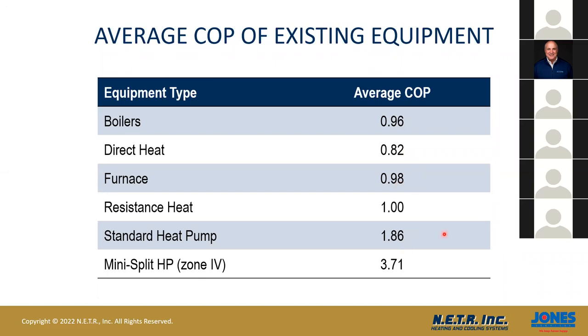When you look at a standard heat pump, and there are a lot of different manufacturers out there now that sell standard heat pumps that claim they heat at low temperatures, when you go look at the COP at these low temperatures, it's very low. When you look at a typical 4 or 5 zone heat pump from mini split manufacturers, you're going to see around 3.7 at 47 degrees. This one is probably about 1.8 at 47 degrees. So you have to be aware of the coefficient of performance for the existing equipment.